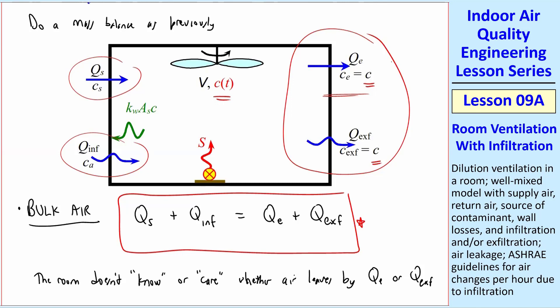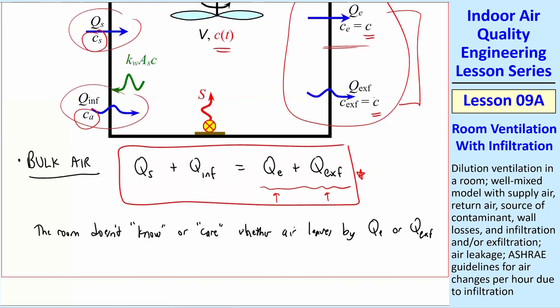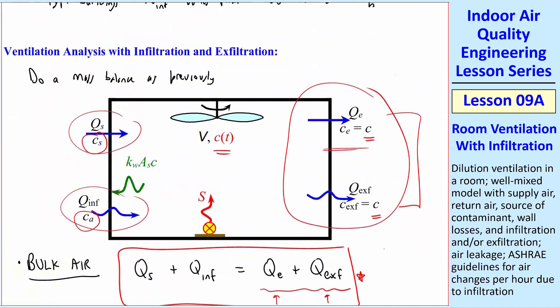But since they both have C as their concentration, it doesn't really matter. So Q_E and Q_EXF often occur together in an equation because they both have the same mass concentration. But Q_S and Q_INF are different because the C concentration is different. It's C_S for the supply and it's C_A for the infiltration. So keep that in mind. This will become important later when we do recirculation.